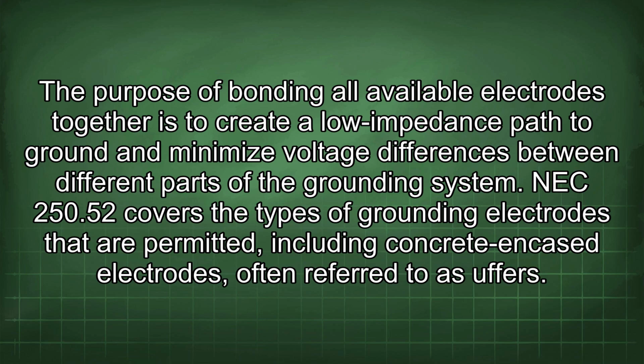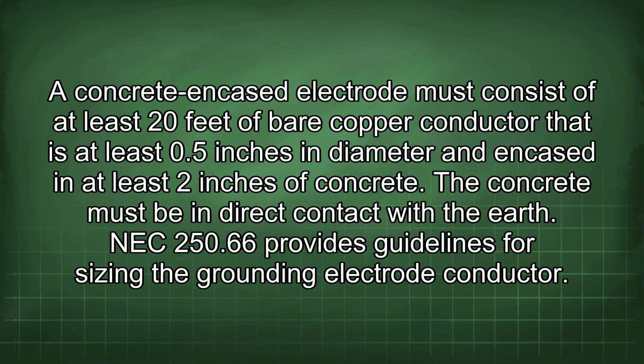NEC 250.52 covers the types of grounding electrodes that are permitted, including concrete encased electrodes, often referred to as Ufers. A concrete encased electrode must consist of at least 20 feet of bare copper conductor that is at least 0.5 inches in diameter and encased in at least 2 inches of concrete. The concrete must be in direct contact with the earth.